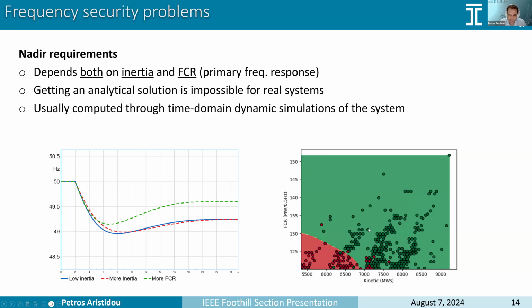And with green, we can see that these are cases where the system is secure. And with red, we can see the cases where the system was not secure. Now, the problem is that in the red area, there are some green dots, and in the green area, there are some red dots. So there is no clear way to say that if we have a kinetic energy above this amount and frequency containment reserves above this amount, for sure we're going to solve the problem or not, because the red dots are intermingled with the green dots.